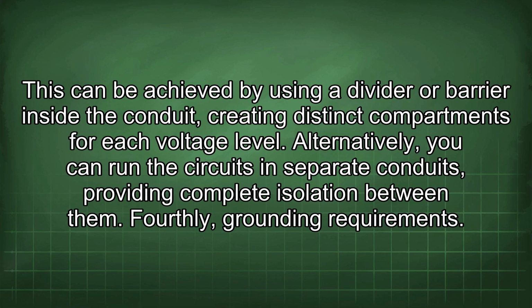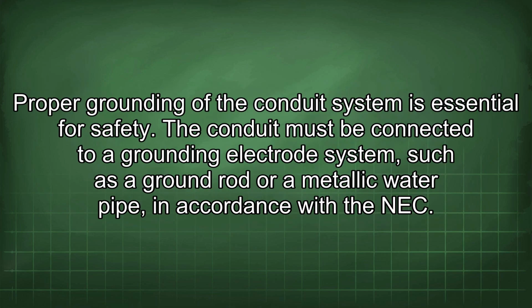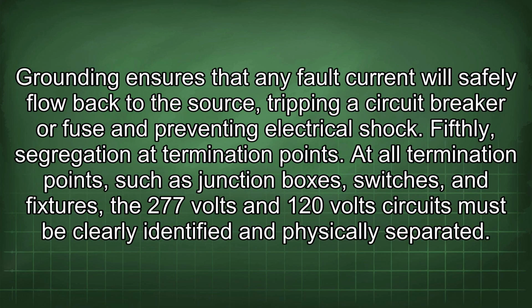Fourthly, grounding requirements. Proper grounding of the conduit system is essential for safety. The conduit must be connected to a grounding electrode system such as a ground rod or a metallic water pipe, in accordance with the NEC. Grounding ensures that any fault current will safely flow back to the source, tripping a circuit breaker or fuse and preventing electrical shock.